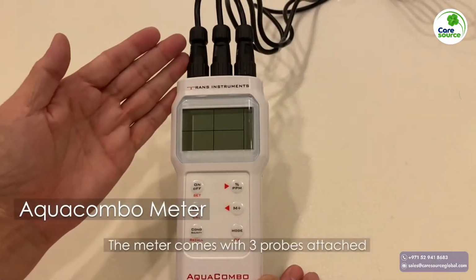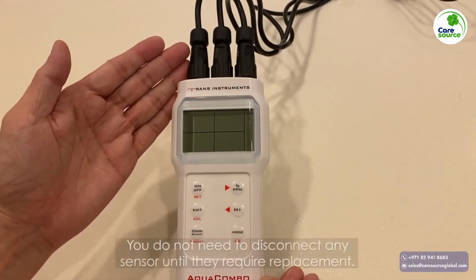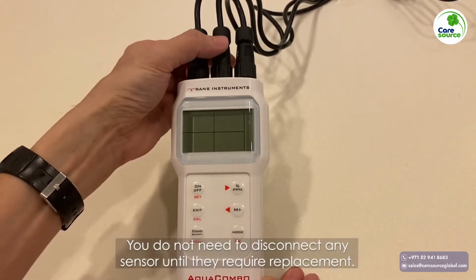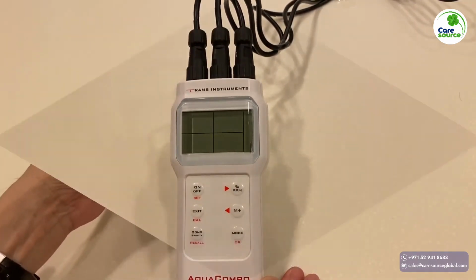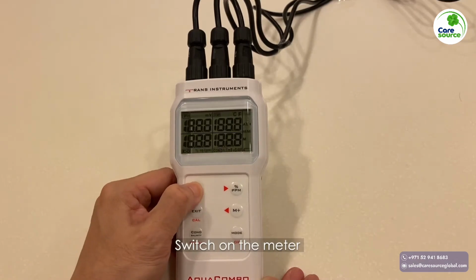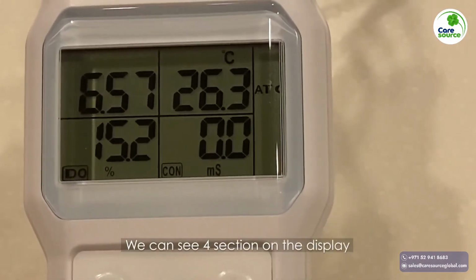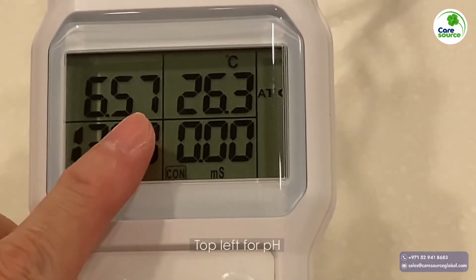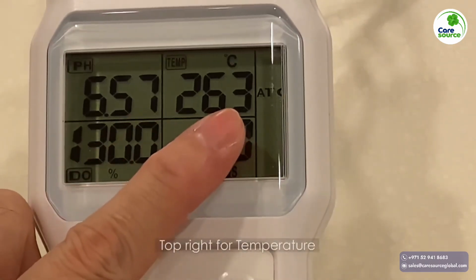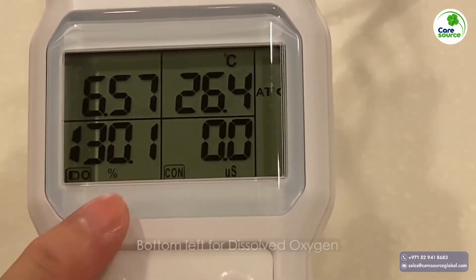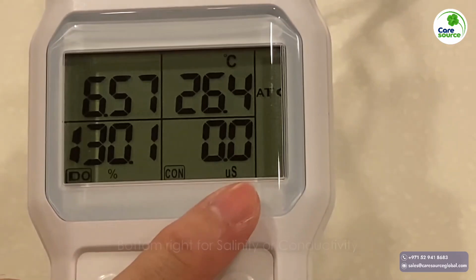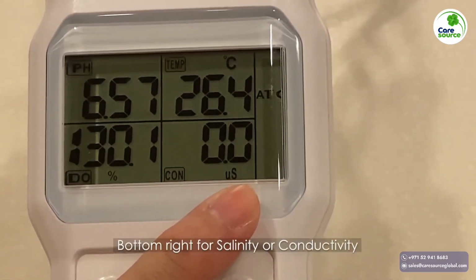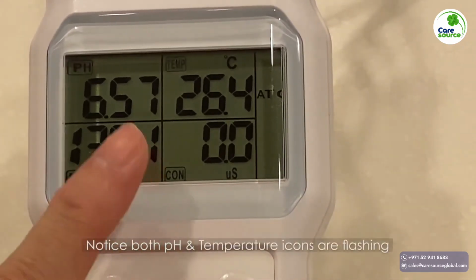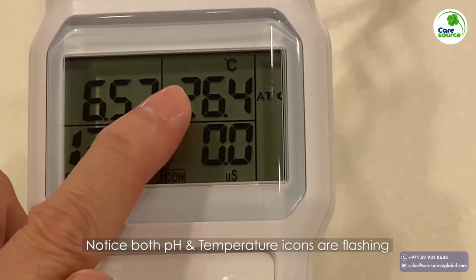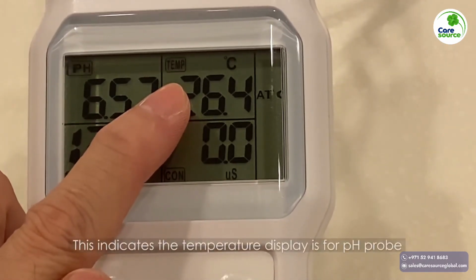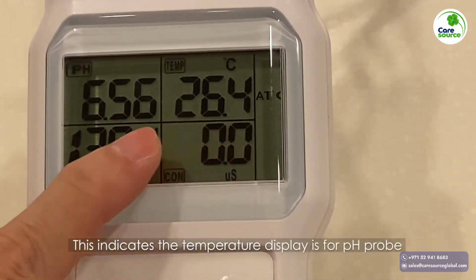The meter comes with 3 probes attached. You do not need to disconnect any sensor until they require replacement. Switch on the meter. We can see 4 sections on display. Top left for pH, top right for temperature, bottom left for dissolved oxygen, bottom right for salinity or conductivity. Notice both pH and temperature icons are flashing. This indicates the temperature display is for the pH probe.